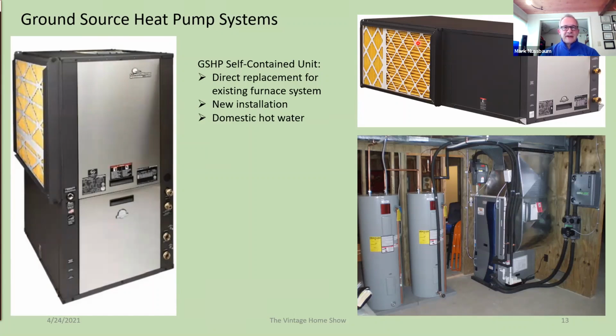You can put in a new installation. And like most of these heat pumps, it has the ability to generate domestic hot water, which happens in the summertime. It's almost free because it's essentially taking heat that would have been discarded to the ground, or rejected to the ground, and rejects it to a tank. Here's a setup that shows that.